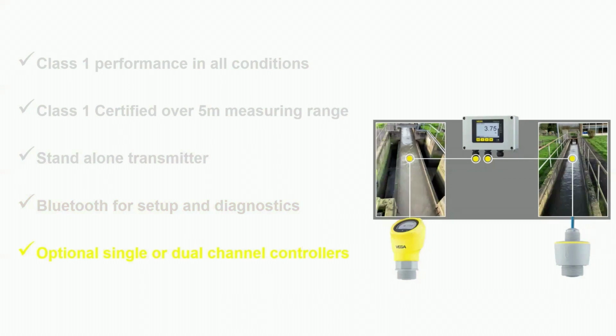Here we've got a couple of different applications. On the left hand side is your spill point to the storm tanks, your EDM, your UMON3 - there we've selected a radar that has a display in the head, coupled up with a radar on the right hand side on an open channel flow application. We've mixed and matched here, going with a fully potted cable version, and those two sensors feed back to one controller, allowing you to maximize the functionality of the controller and the space in the panel. You've got multiple totalizers and an 8 gig SD card - if you're monitoring data at 1 minute intervals, that's 185 days worth, nearly 6 months of data. It really offers a huge amount of flexibility as MCERTs applications continue to evolve from not just open channel, but to EDM as well.